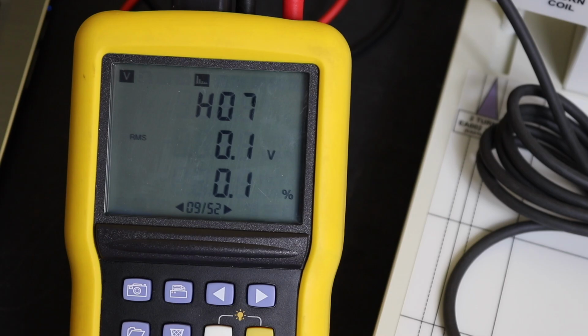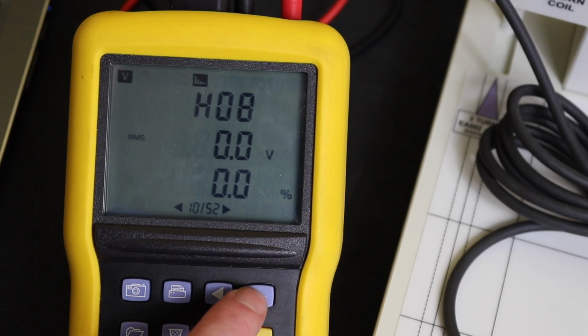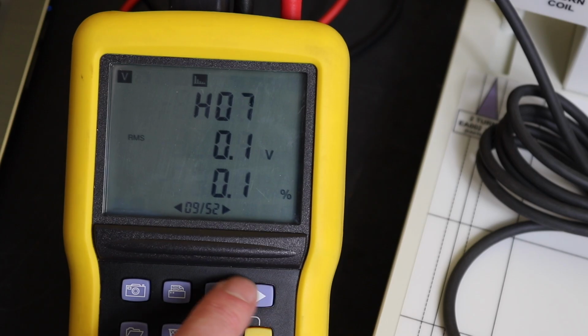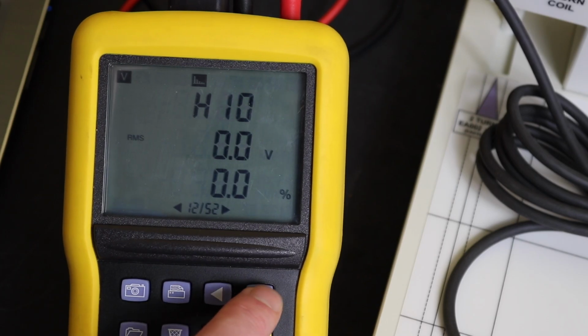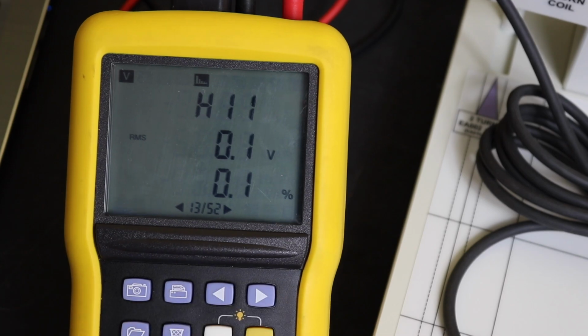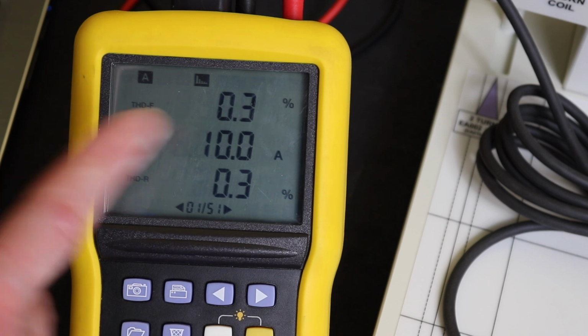I have to hook it up to something else to pick up. That's interesting. Got a slight harmonic, 7th harmonic there. So we've got some odds. Yeah, odd harmonics, very, very small values. So that's there. We can also do that with the current, exactly the same.